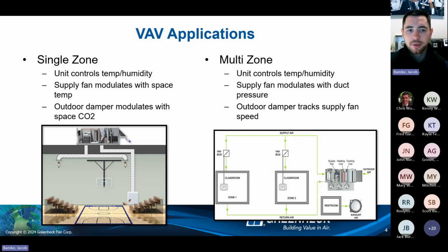And when we look at the supply fan in this case, typically we're modulating off of space temp. So we have varying levels or loads of space temp requirements. As more people come into the gym, more people leave the gym, it changes. We want to make sure that we can move enough air to control that temperature precisely.